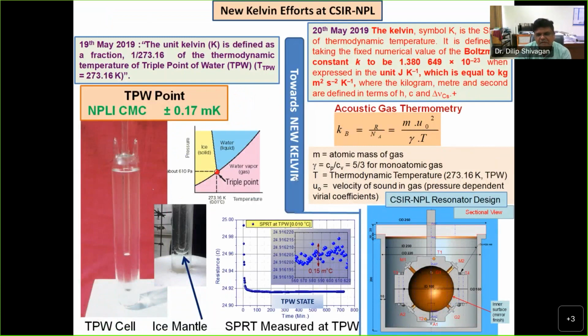In acoustic gas thermometry, the square of the velocity of sound is directly proportional to thermodynamic temperature. In a very fine resonator, very high purity argon gas or monatomic helium gas is placed, and then acoustic resonances are measured, which are proportional to temperature.